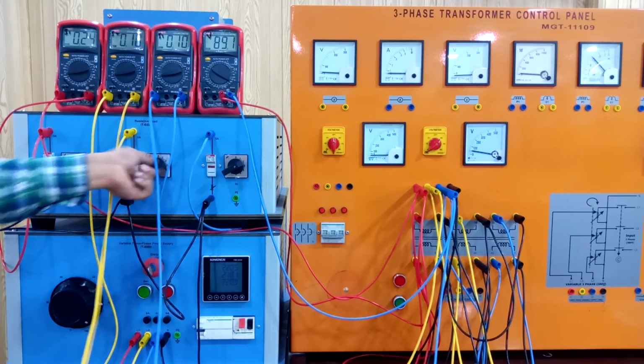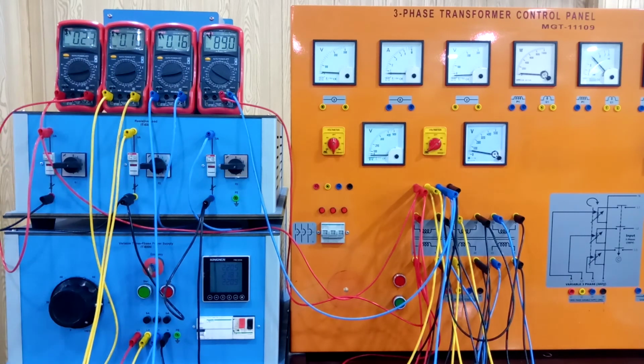Again for the third reading: 0.24 on the first phase, 0.15 on the second, 0.15 on the third, and the voltage has decremented to 89. The previous one was fluctuating between 89 and 89.1, and now this is almost the same, but we can still see the voltage has decreased.